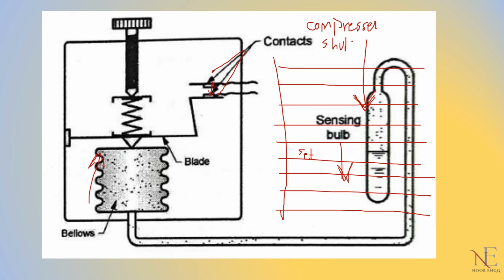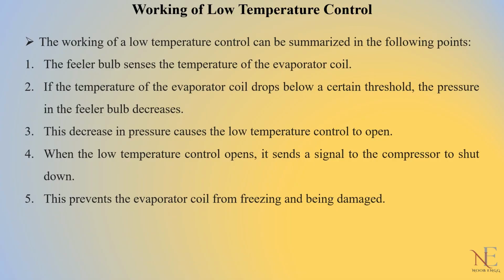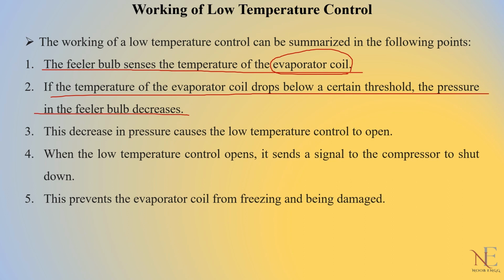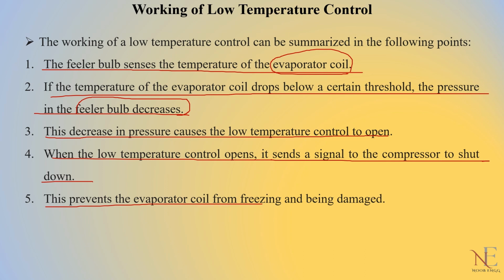This is the simple working of a low temperature safety control. First, the feeler bulb senses the temperature of the evaporator coil. If the temperature of the evaporator coil drops below a certain threshold point, the pressure in the feeler bulb decreases, not in the bellows. The decrease in pressure causes the low temperature control to open. When the low temperature control opens, it sends a signal to the compressor to shut down. This prevents the evaporator coil from freezing and being damaged. This is the simple working of a temperature control.